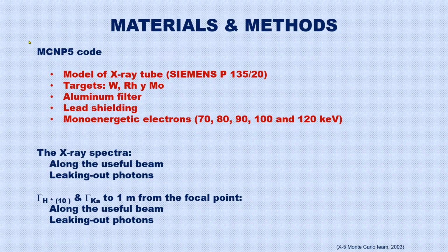With the model inside the MCNP code, we simulate the transport of the electrons through the target and the X-ray production in the target, and the transport of the X-rays outside the X-ray tube along the useful beam, and take into account also those photons that leak out from the X-ray tube head. With the spectra, we calculate the gamma factor for the ambient dose equivalent and the gamma factor for the air kerma at 1 meter from the focal point along the useful beam, and take into account the leak out photons from the shielding of the X-ray tube.